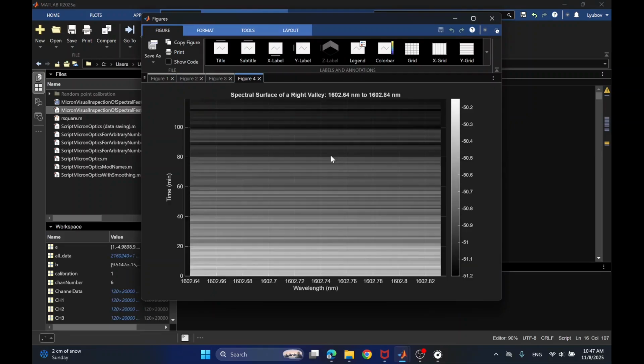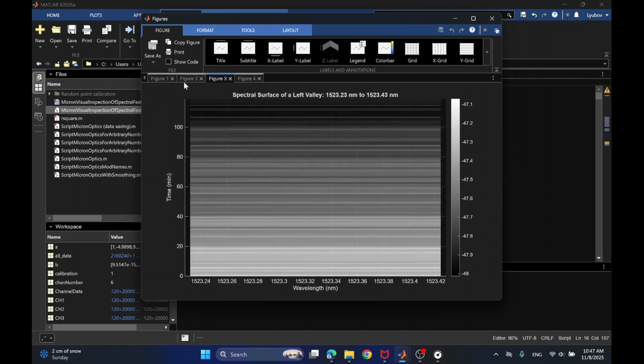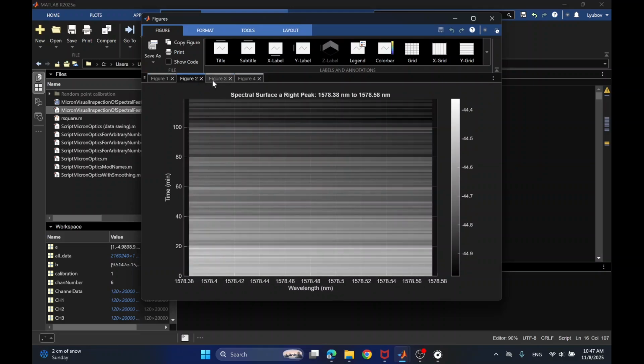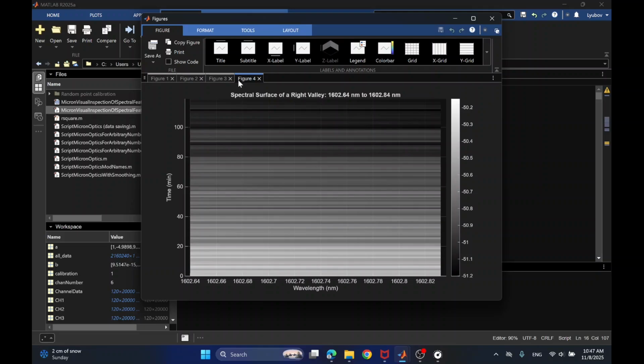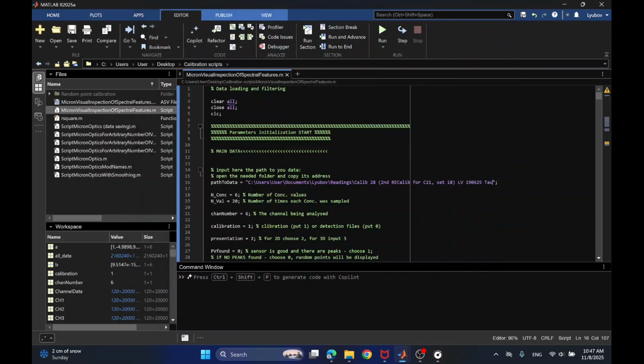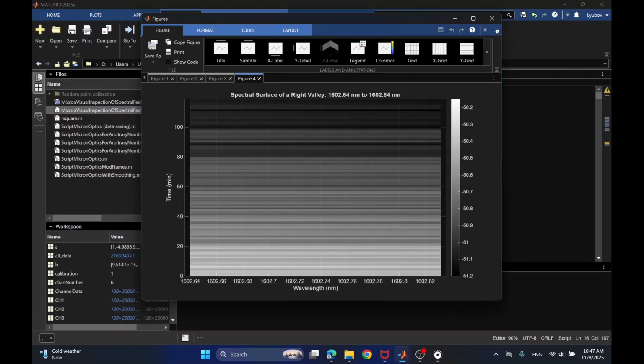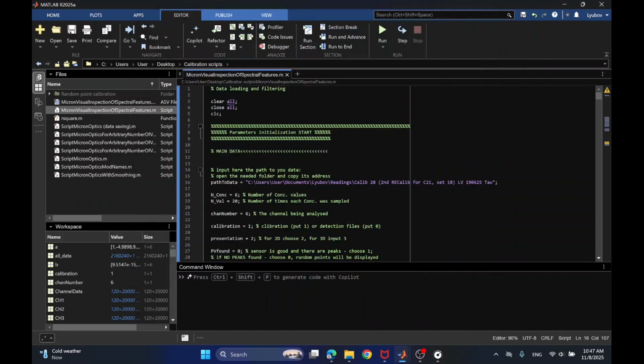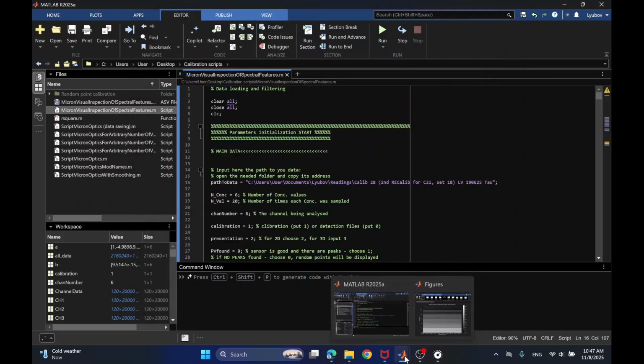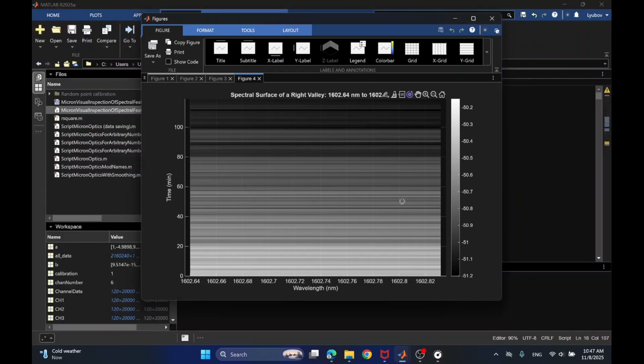And here are the results for the very same probe, for the very same channel, but different concentration, which is the lucky one. And you see that in reality the probe is really good. Remember, these are random points. And still, we have a very, very smooth gradation. Sometimes not very smooth, but you see that this is a signature of a really good probe. So it means we just saved time and saved the probe, which had a bad day, but now it's back in line and can be used.